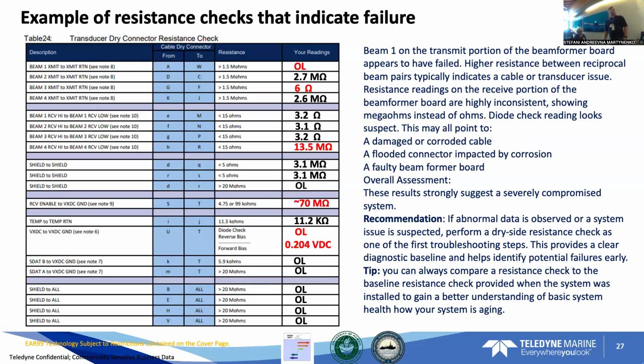And this is an example of a bad reading. Like I said, you have an open here, which would be an indication that for beam 1 transmitting on the beamformer board, there's probably something damaged with it. The same with beam 3 here, which is only 6 ohms. That's kind of suspect when it should actually be mega ohms. These are all kind of the same, except this one is 13.5 mega ohms, and again, that's a sign that something's going on. It could be corrosion, or something could have happened to the cable. Just things to look out for. These are all troubleshooting tips that will help you troubleshoot what's going on with your system.